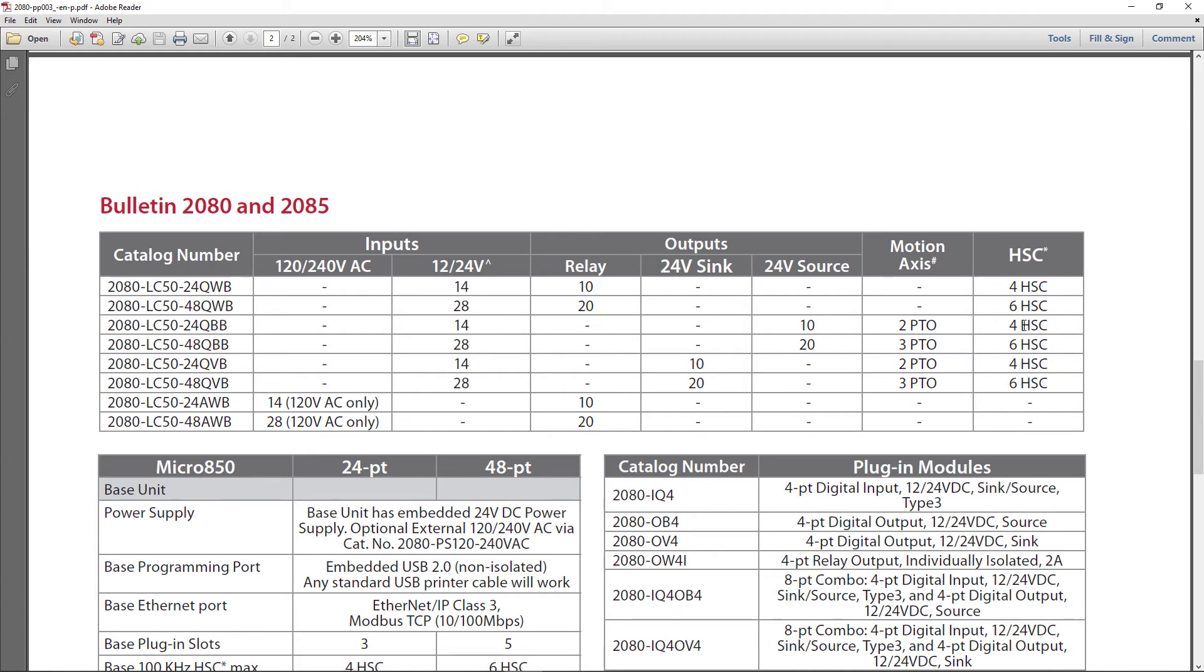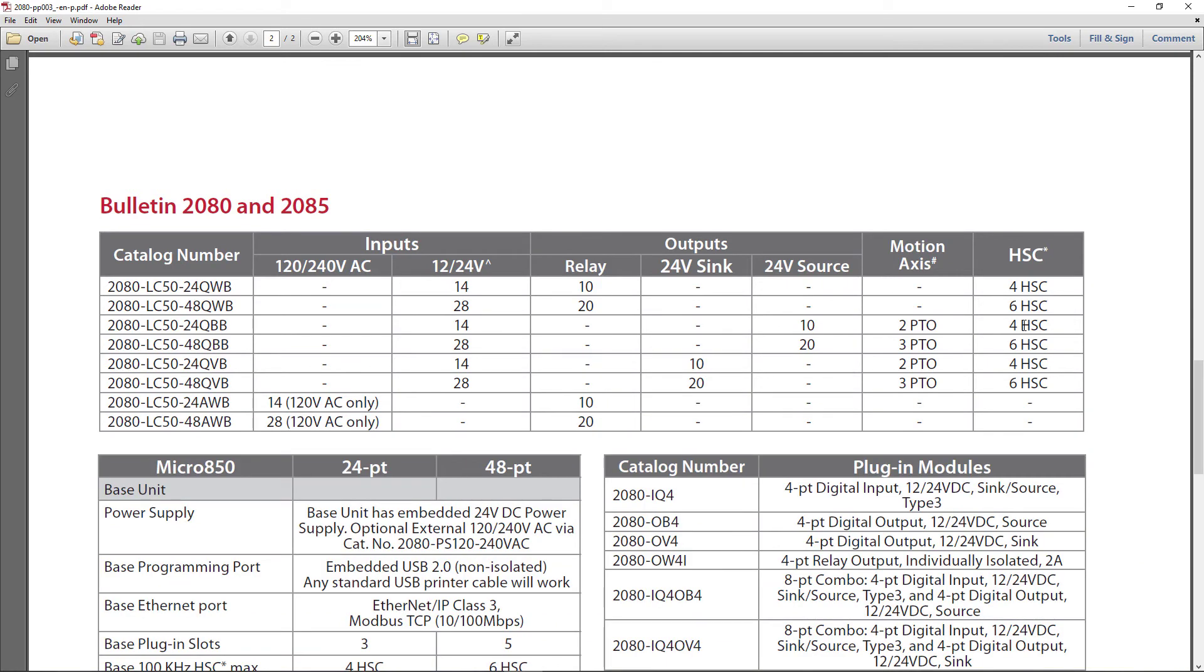The pulse train output can put out pulses faster than you could generate with a standard output, and this is done for the sake of motion. The motion instructions, the motion functions with Micro 800, are very similar to Control and Compact Logix. Once you turn the dog loose, it's loose. Once you initiate a move, it's on its way and it's independent from that point on of what the processor is doing, to an extent.